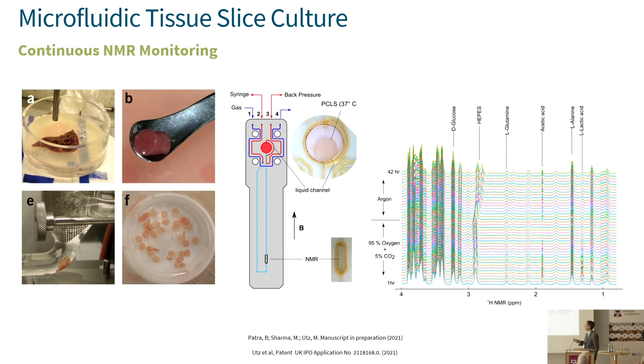One point I should mention is that we are interested in measuring changes. We want to see metabolic rates. We're not particularly interested in absolute concentrations. And if you want to see change, then you need to allow time for it to occur. That leads to a problem here, because in order to provide the tissue with sufficient oxygen, you have to maintain a minimum flow rate. If you go below that flow rate, the tissue consumes oxygen more rapidly than you supply it. After all, we're supplying it through an aqueous solution, which is terrible. Right? That's why we have blood, because oxygen solubility in water is terrible. So you need to maintain a high flow rate. If you have a high flow rate, everything that happens in the tissue gets diluted into a massive amount of perfusion fluid, and you never see any difference. You always measure the same concentrations for everything.